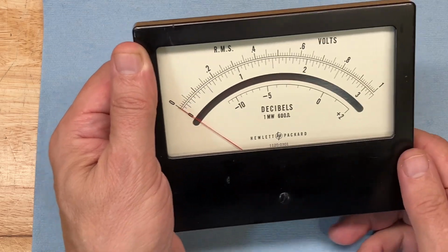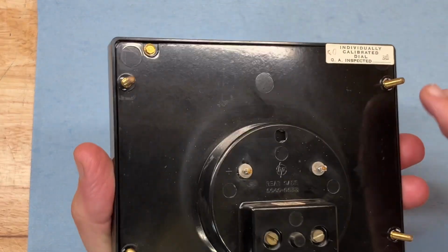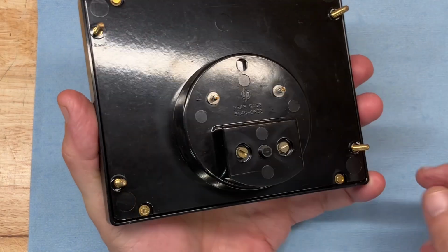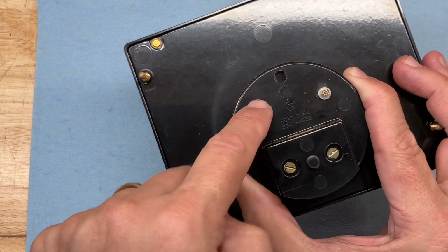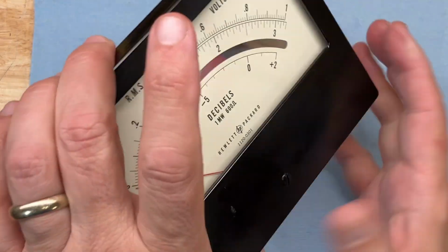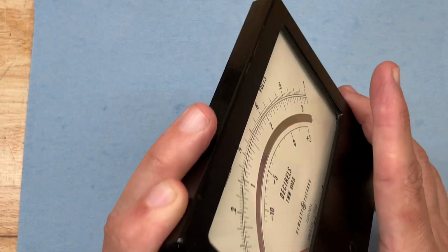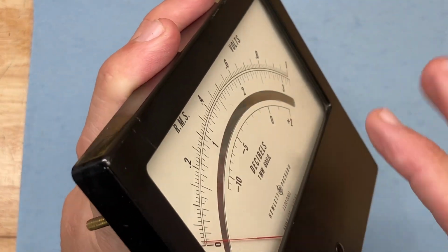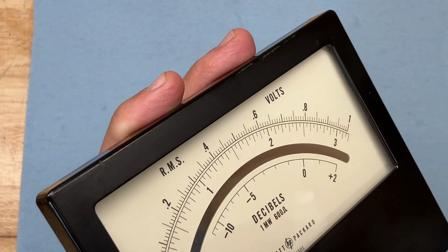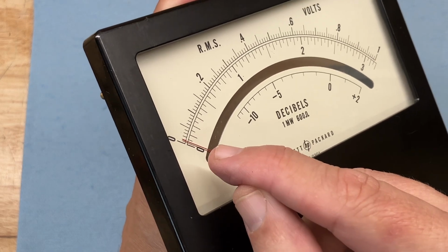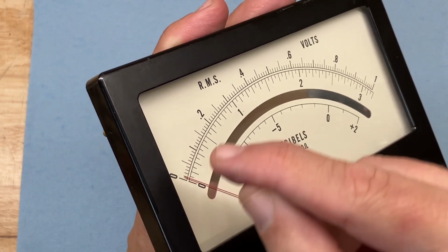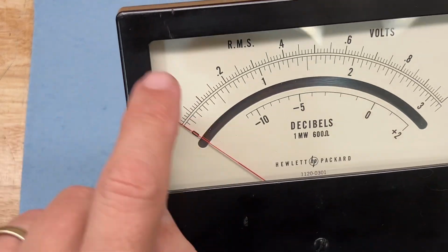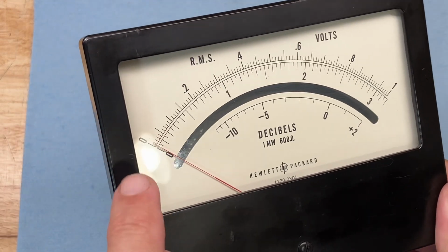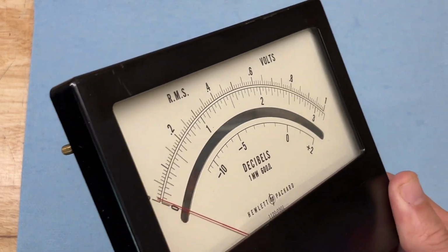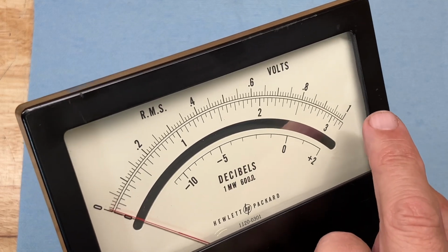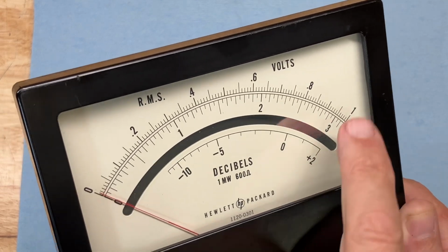Okay, so I have very carefully removed the 4 mounting screws that hold the meter movement in place in the instrument and unsoldered the 2 meter terminals. I don't know if this shows on camera, but if I look very closely, the needle of the meter, when it's at 0, is completely free of the white face of the dial. But as the meter gets close to full scale, it tends to stick near the 1 on the dial.